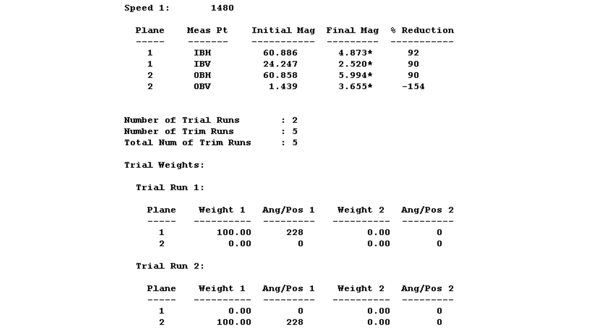After that, I proceeded with two-plane balancing. The vibrations reduced drastically, and now this fan is running very smoothly.